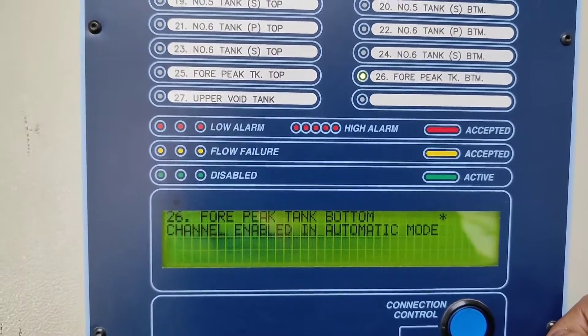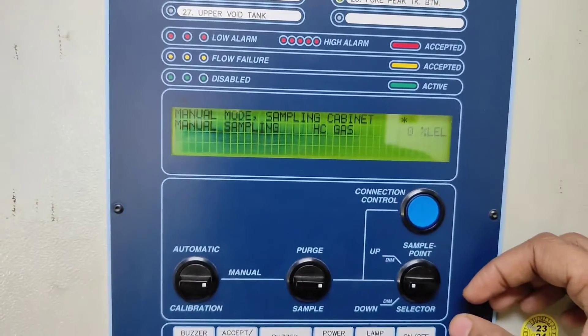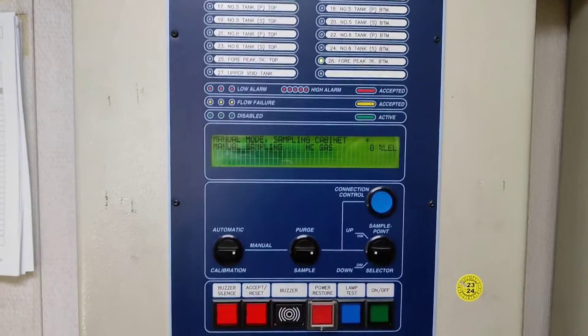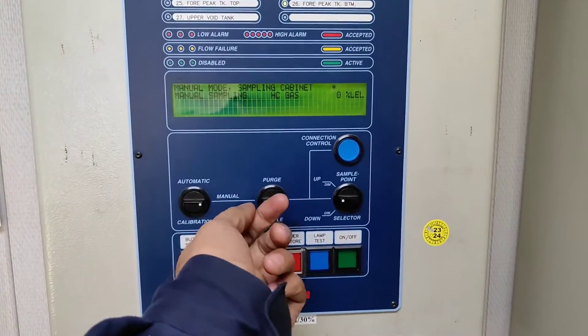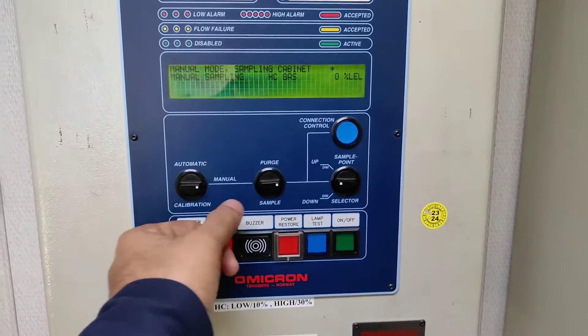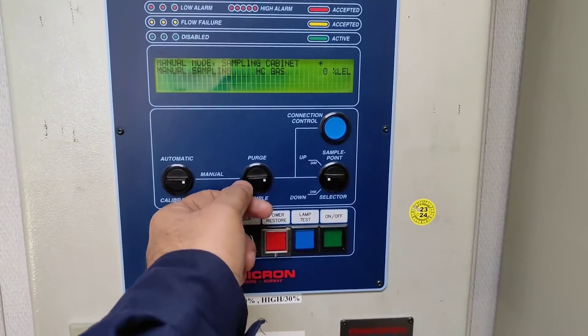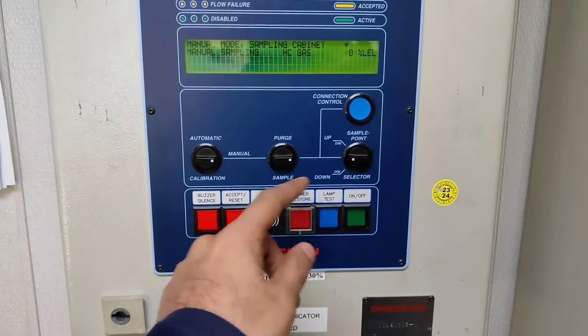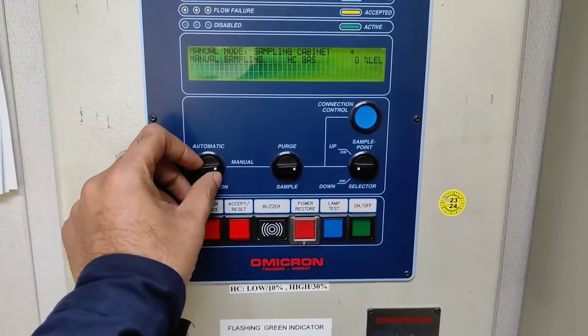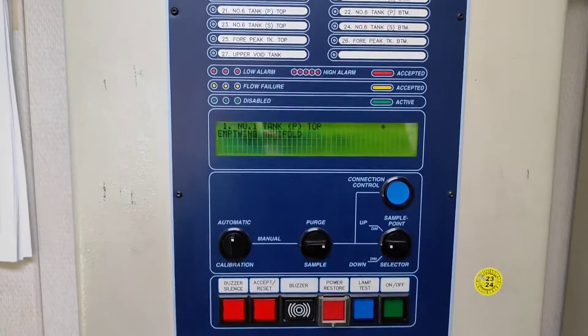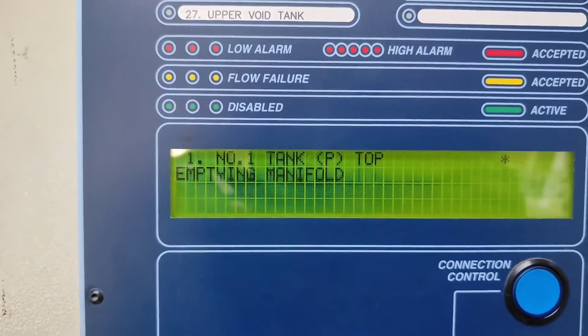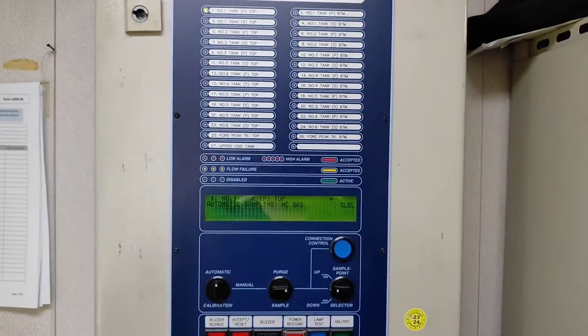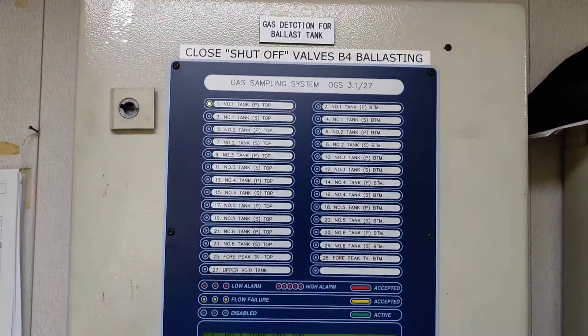Going to number 26 — the last one — and press enable: 'channel 26 enabled in automatic mode.' So all tanks are connected now. If you want to purge, turn the selector up. If you want to take a sample manually or do any other operation, put it in manual mode. Once done, I'll put it back in automatic mode. It now says 'empty manifold, starting from number one tank' — no alarm, it is running.